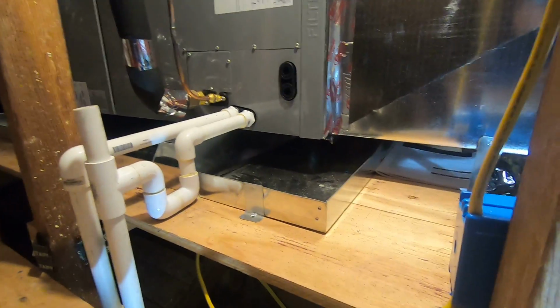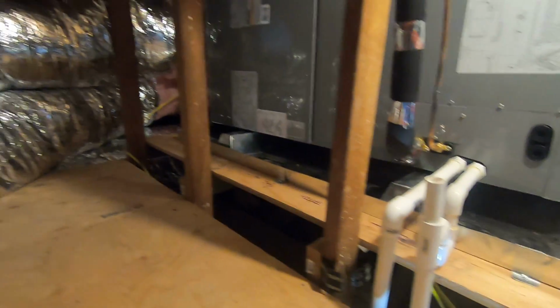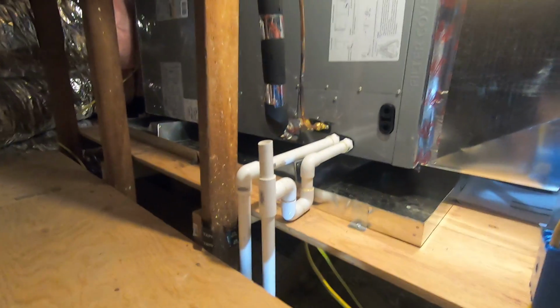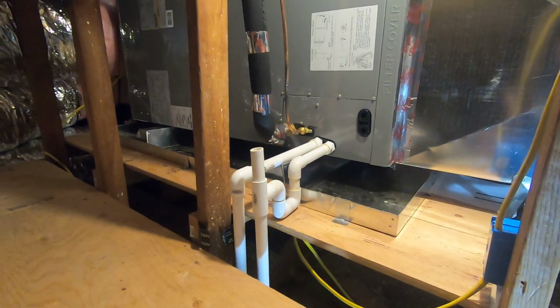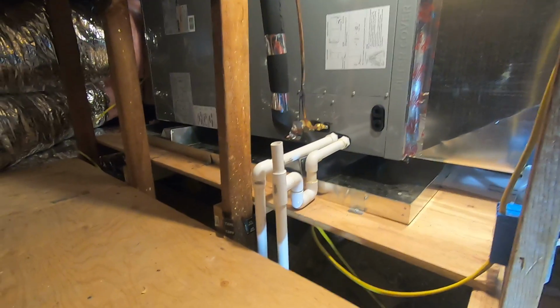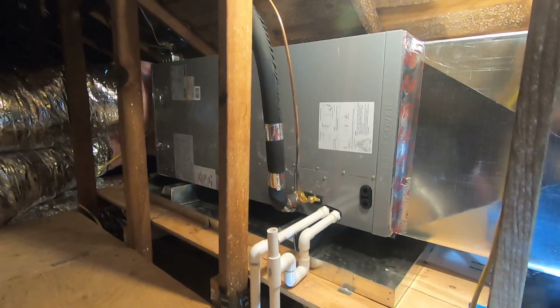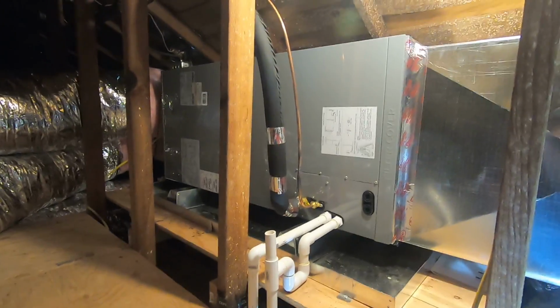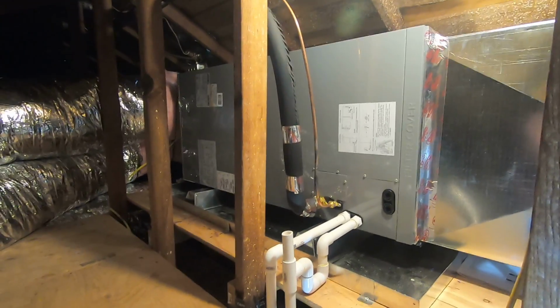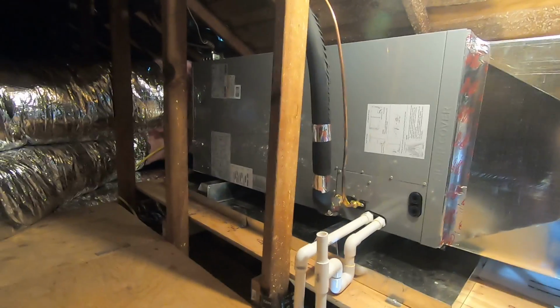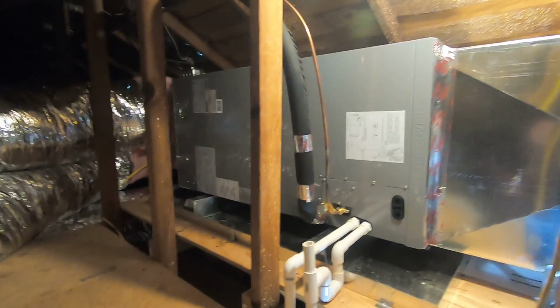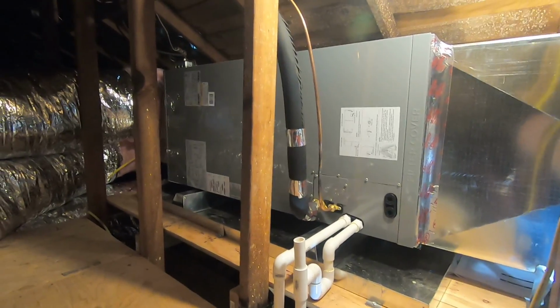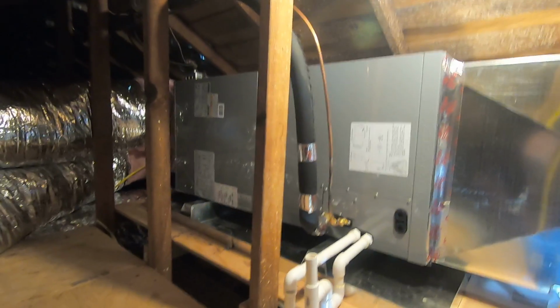Underneath the unit we have a drain pan that encompasses the whole bottom of the unit, and we have the drain lines. We have a primary and secondary drain line, and then we have a shutoff switch on that. This is a variable speed fan coil. It's matched with a variable speed slimline condenser or heat pump condenser outside, so it will fluctuate its speeds. This is a very quiet unit, runs about 60 decibels.